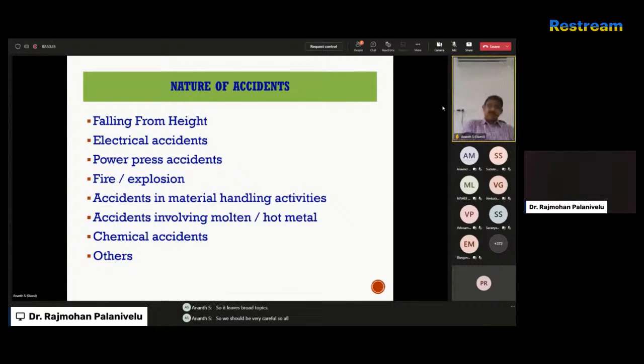All electrical machinery should be provided with an earth leakage circuit breaker, ELCB. People generally say MCBs are already provided, but MCB is only to safeguard the machine against high current or high load usage. ELCB is the only remedy for safeguarding humans, because if any fault current occurs, the ELCB will automatically trip the circuit, cutting the passage of current to the victim. That is how we can avoid accidents.